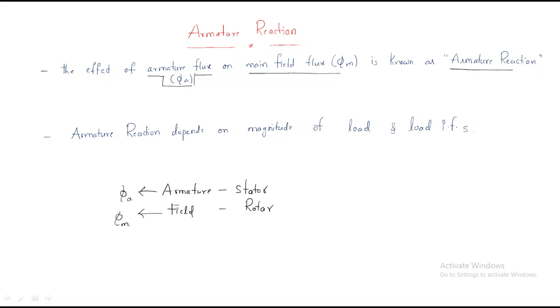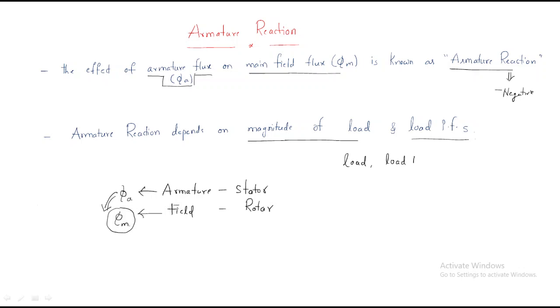The armature flux will affect the main field flux, and this effect is known as armature reaction. The word 'reaction' implies a negative effect — the flux is affected adversely. Armature reaction depends on two things: the magnitude of the load and the load power factor. These two factors are very important in the case of armature reaction.